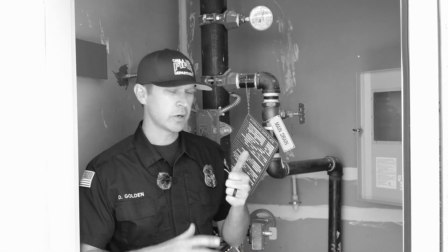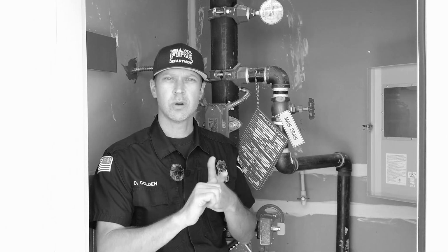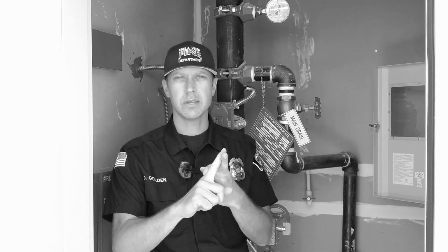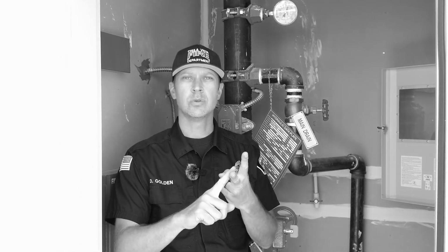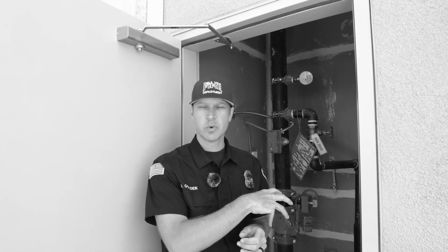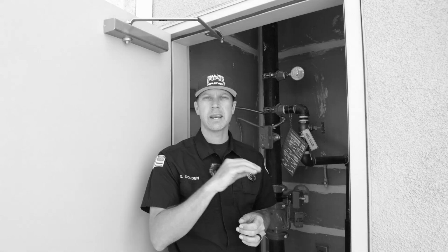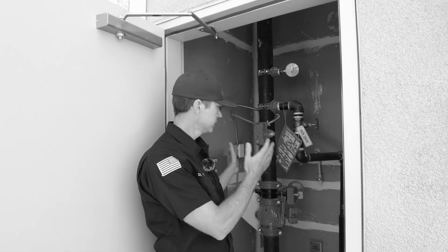Okay, so we located our fire protection system. We've confirmed water's flowing in the system. While we have no active reports of fire, the next step is to, one, locate where the water's flowing from, and two, actually confirm we have no active fire. Okay, so firefighters have been sent to the room where there's a fused sprinkler head and have confirmed there is no fire. Now we return to the system riser to try to shut it down.